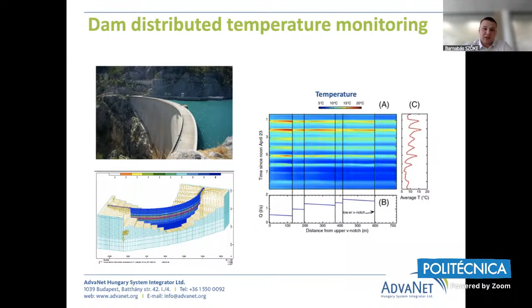Because it's spark-proof, we can use it for leak detection. We can use it to measure the displacement of gas pipes, and also for dynamic line rating and for measuring the temperature distribution of transformers. With FBG, we can measure the temperature of every winding of the transformer, and we can also measure the temperature of the oil of the transformer.